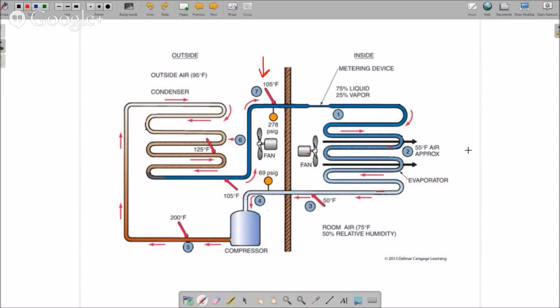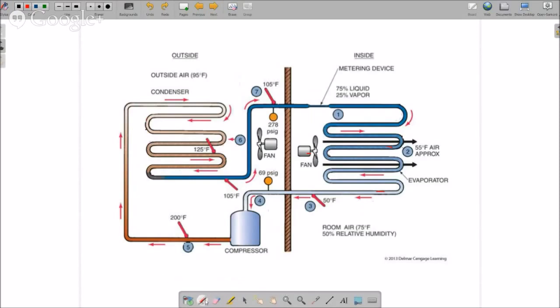You are going to have very high superheat. Just remember the pressure-temperature relationship - when pressure goes up, temperature goes up, and vice versa. We're not going to get into that in this example, but I want you to realize what happens within the system to the refrigerant itself as we go through an undercharged system. Now let's take a look at an overcharged system.